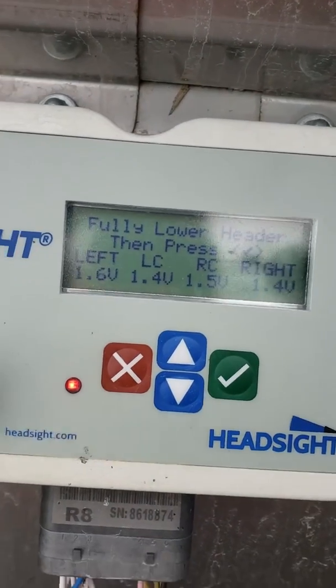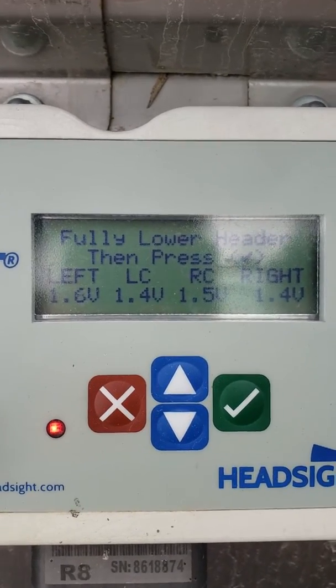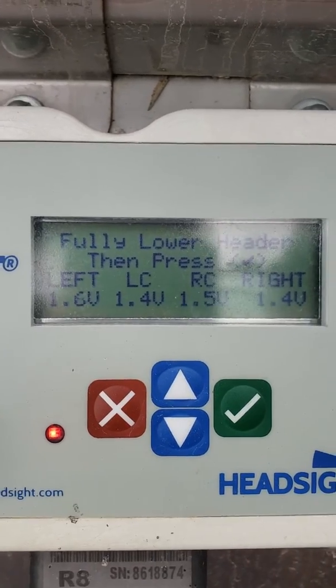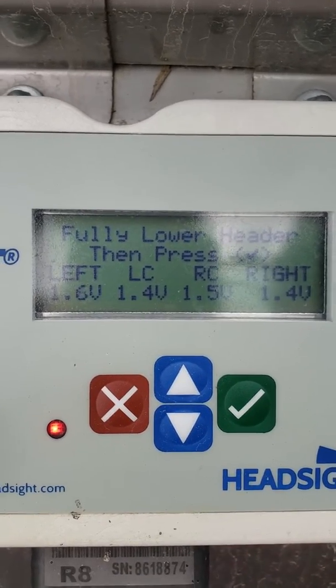Down on the Headsight box, our head is fully lowered and we can see we have less voltage on all four sensors. This is a good opportunity to double check and make sure you've got voltage on all of your sensors. If one of the sensors didn't change voltage, you probably have a wiring issue or a bad sensor.